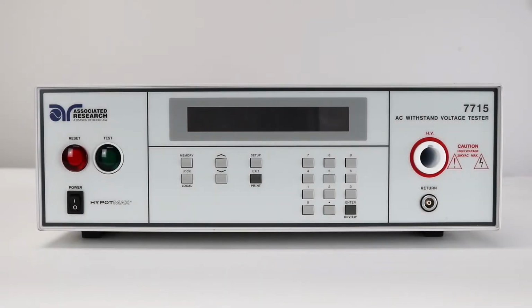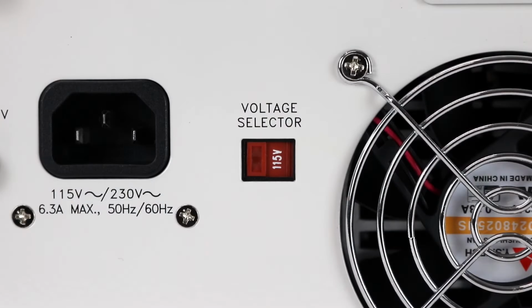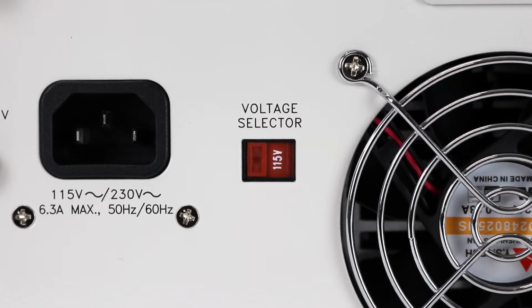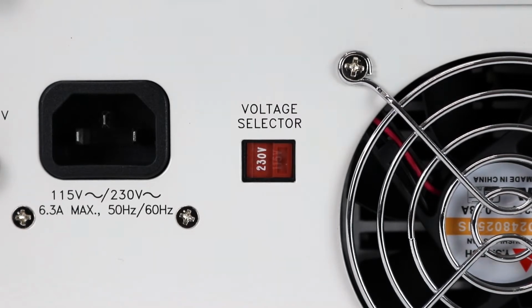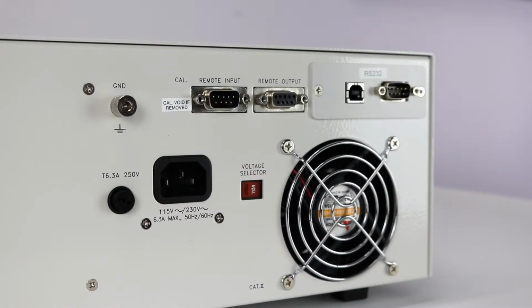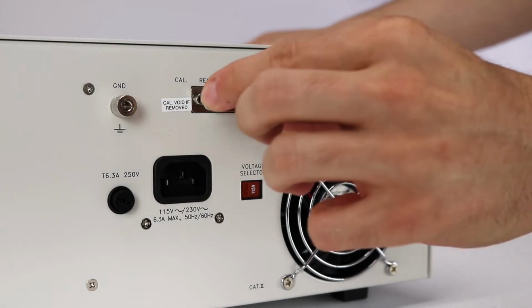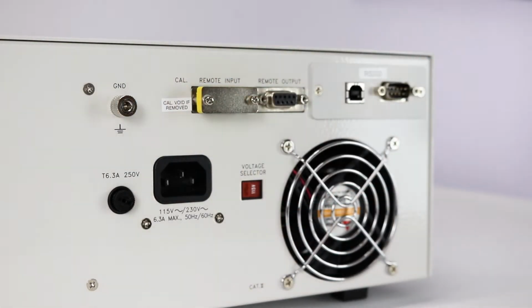First, you'll need to power up your HypotMAX instrument. Check to be sure the correct input line voltage has been selected on the rear panel, either 115 volts AC or 230 volts AC. Insert the remote interlock key into the remote input terminal on the rear panel. The instrument will not output voltage unless this interlock key is properly plugged in.